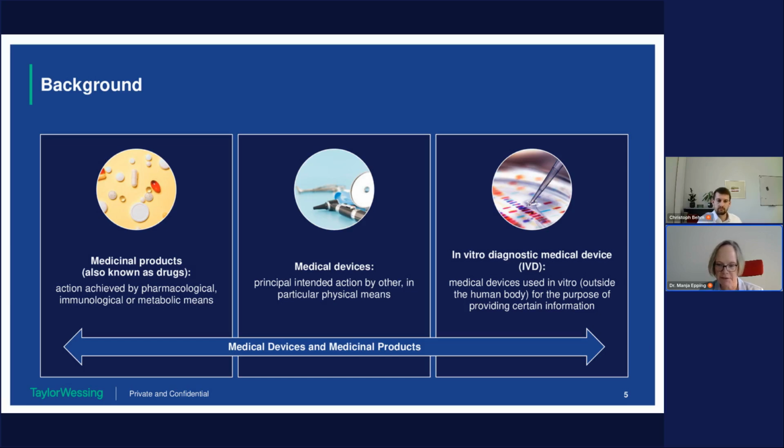In vitro diagnostic medical devices, as the name already states, are a subgroup of medical devices. These are, for example, reagents or other assays, including software, which are used outside the human body, in vitro, not in vivo. And the purpose is to provide certain information on certain circumstances in the body, certain biomarkers, certain properties that are important for the therapy.